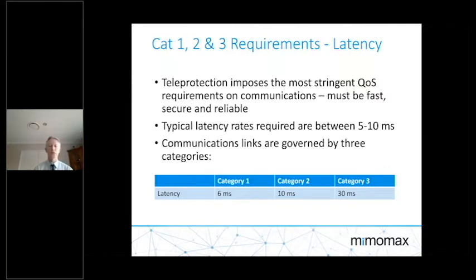So we look at these communications links and see that they're governed by 3 categories. Latency is one of the key aspects of those categories: category 1 sits below 6 milliseconds, category 2 at 10 milliseconds, and category 3 at 30 milliseconds. Obviously 6 milliseconds is the most challenging, for category 1.